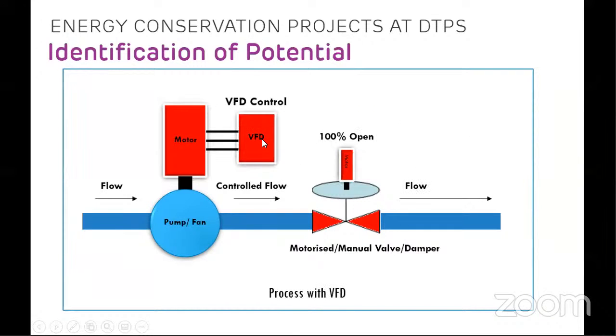So if we install a variable frequency drive on the motor, we keep this valve 100% open and the flow is controlled at the motor speed itself. So the motor speed is varied using VFD. Then the pump or fan flow will be controlled. Therefore, there is no power loss across the valve or damper, and the controlled flow is given by reducing the motor speed, which gives us variable speed as well as energy saving. I hope everything is clear till now. If you have any questions, you may ask. Otherwise, I'll proceed.